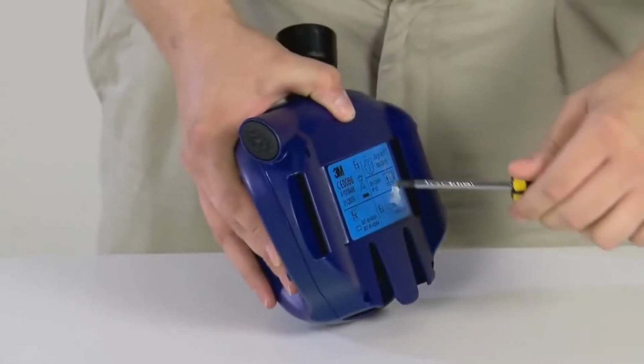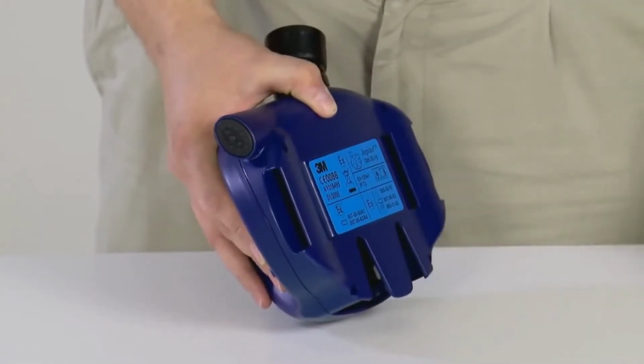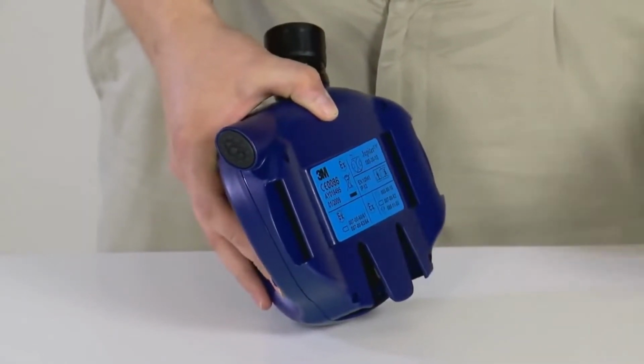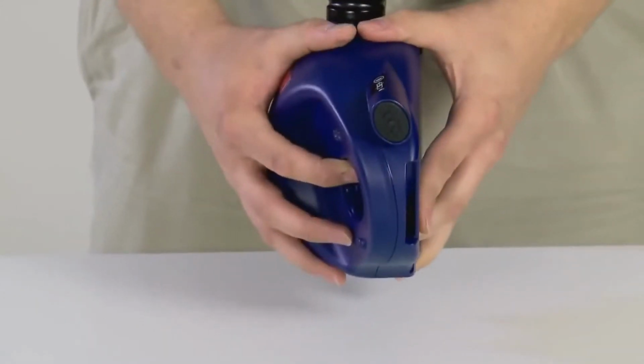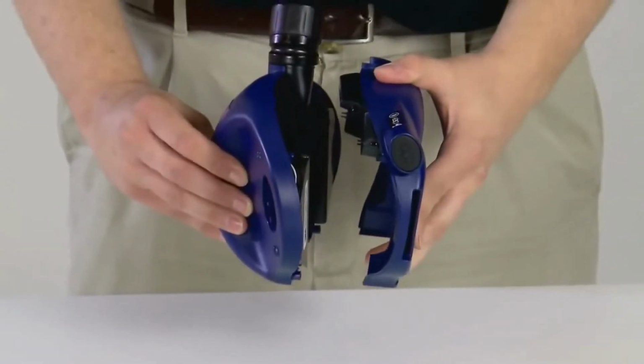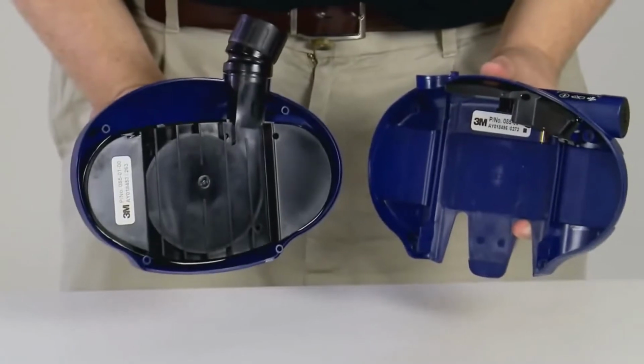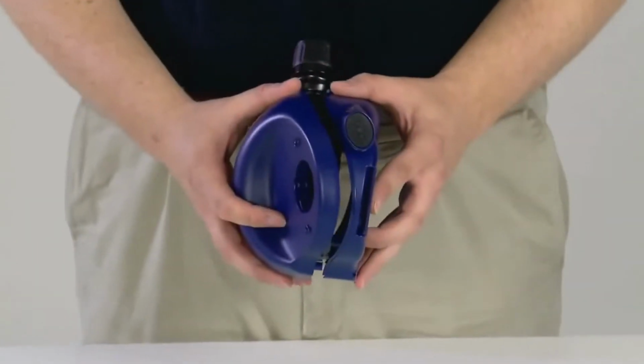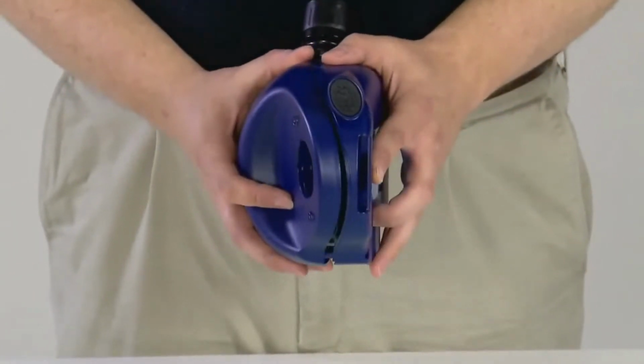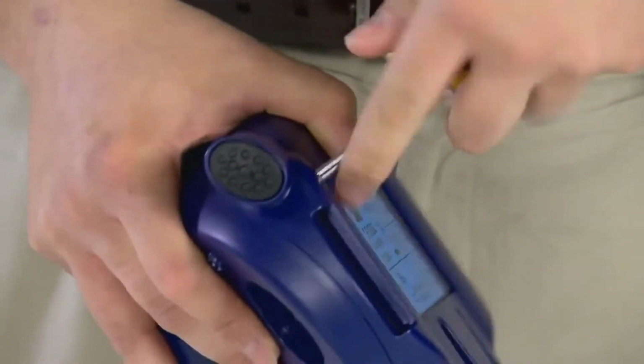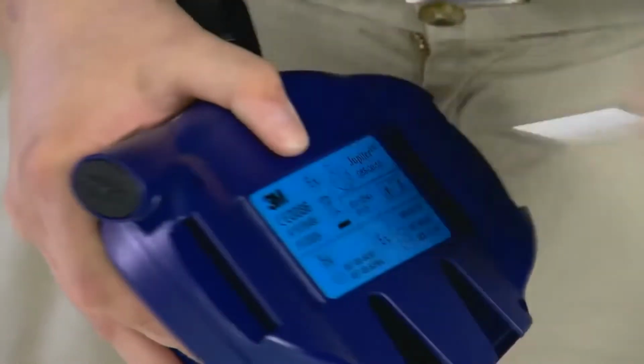To replace either the blower part or the electronics part of the turbo, remove the screws located in all 4 corners. Separate the 2 halves and replace the appropriate unit. Reattach the 2 halves always using the new screws provided. Repeat the calibration steps to ensure that the replacement is working.